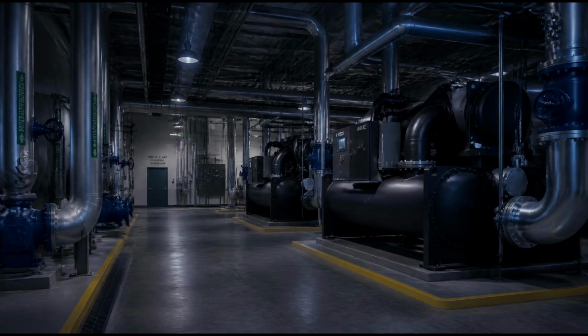There is the condenser water loop, which carries the heat removed by the chiller to the cooling tower, where it is released to the outdoor air. This loop closes the refrigeration cycle and allows the chiller to continue operating continuously. There is the hot water loop in buildings that use boilers for heating, which carries heated water from the boiler to heating coils and radiators throughout the building. The water gives up its heat and returns to the boiler cooler, ready to be reheated.